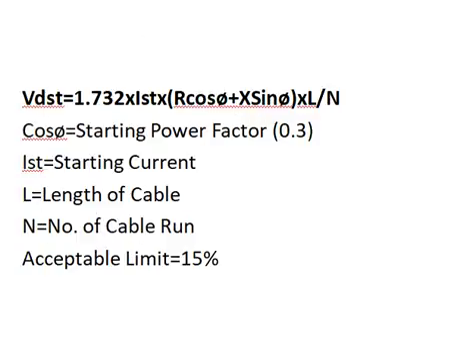Starting voltage drop should be limited within fifteen percent — that means at the motor terminal, the voltage drop during starting should not exceed fifteen percent. The starting voltage drop is calculated by: root 3, into motor starting current, into (R·cosφ + X·sinφ), into cable length, divided by number of cable runs.